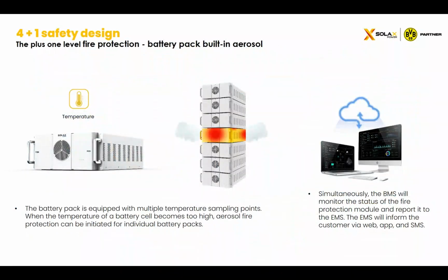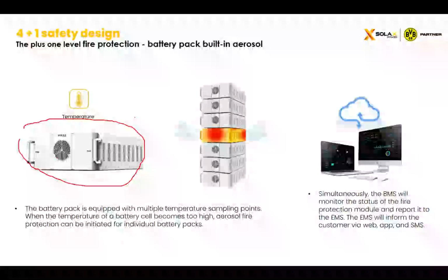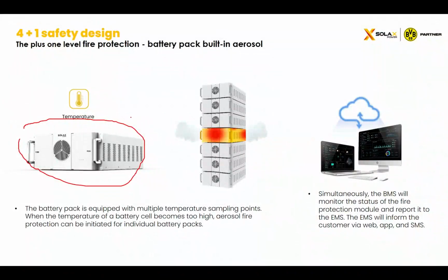And what's more, we also have a +1 safety design. That means each battery module has an internal aerosol in it. The battery pack is equipped with multiple temperature sample points, and when the temperature of a battery cell becomes too high, the aerosol fire protection can be initiated for the individual battery pack. After the aerosol is used, only this battery cannot be used anymore. The only thing the customer needs to do is replace it with another one, and all the rest of the system can still work normally. This design helps us reduce losses if an emergency happens.